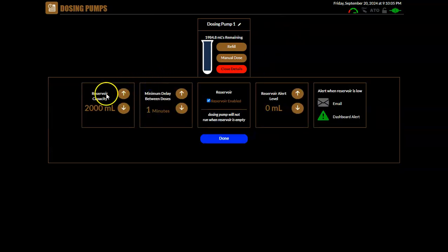We've got our settings. So here is our reservoir capacity. Right now it's at 2 liters. Then there's the minimum delay between doses. Maybe this is kind of like a security thing, so you don't want doses to happen more often than 540 minutes between them. Say you had a custom rule set up that was turning on and off, on and off, on and off. That could be dangerous because it would keep dosing in your system. But with this delay, it won't happen. It'll make sure that after it doses, there will be no more doses for 540 minutes, no matter what happens.